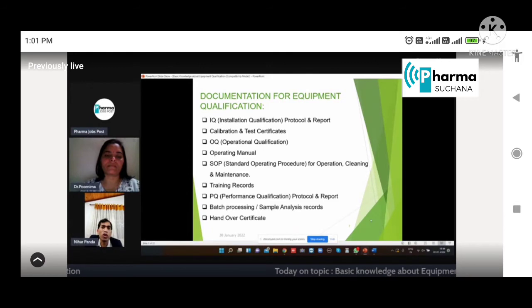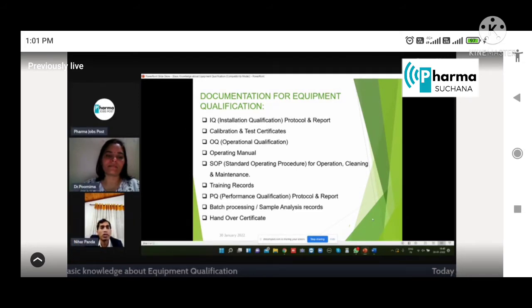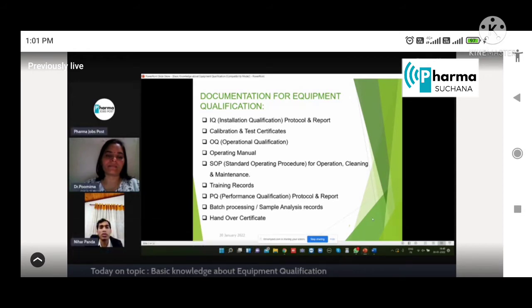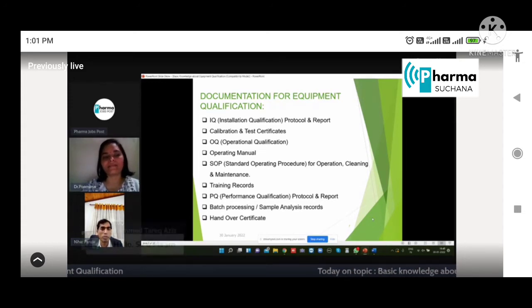What is OQ? OQ means operational qualification. We have to ensure whether the equipment is working or not, and whether it is working as per our requirement and our specification. We have to check all the switches, on, off, and alarm systems, and we have to take screenshots as proof that OQ has been conducted as per our requirement.